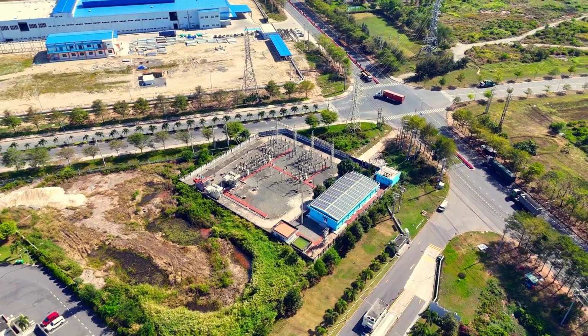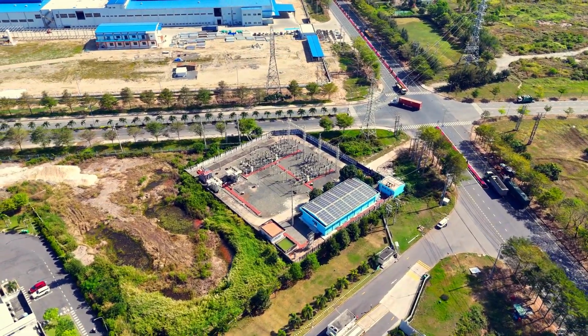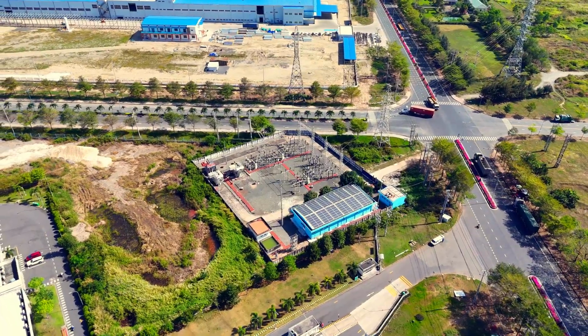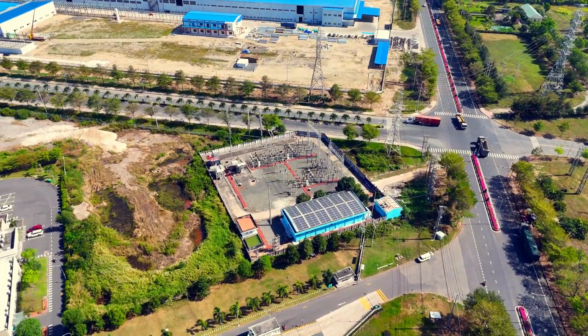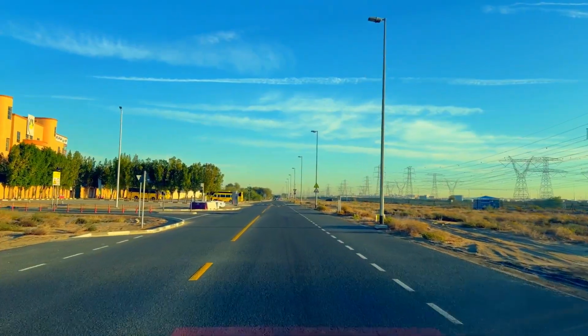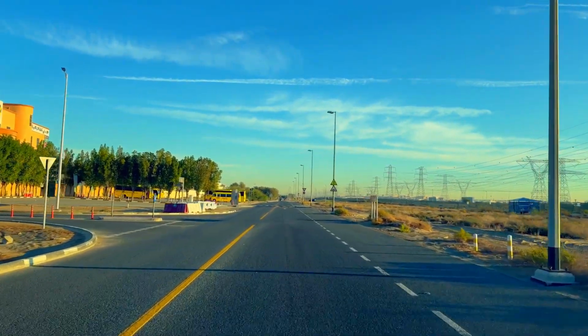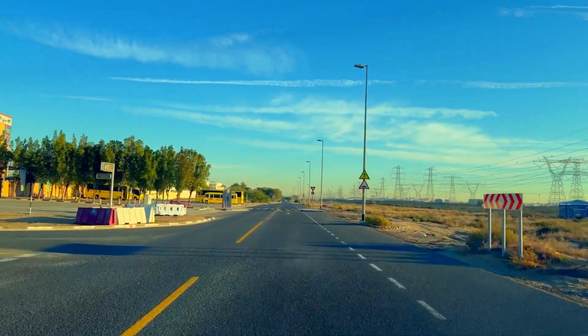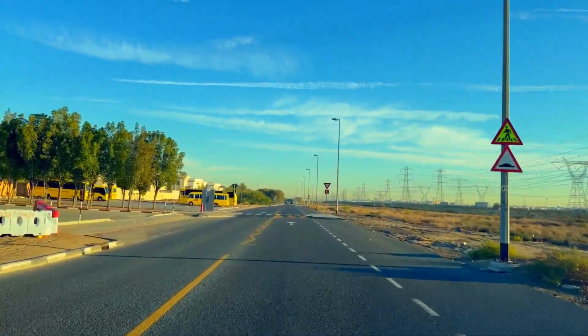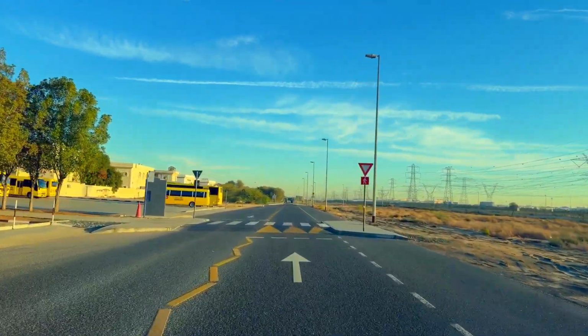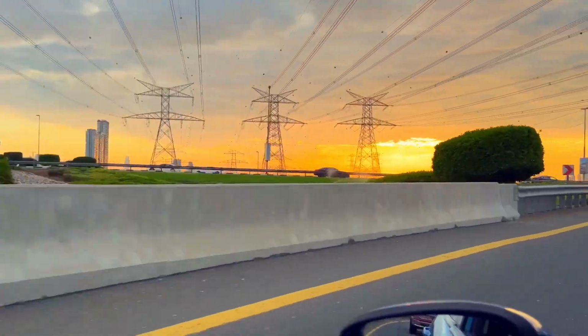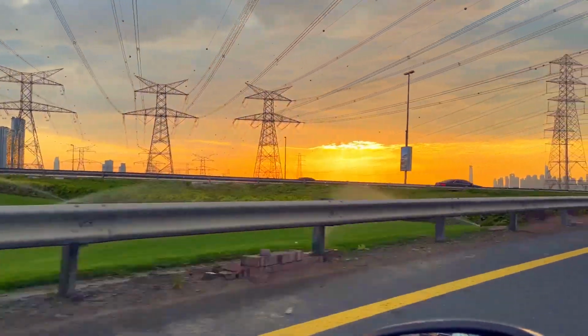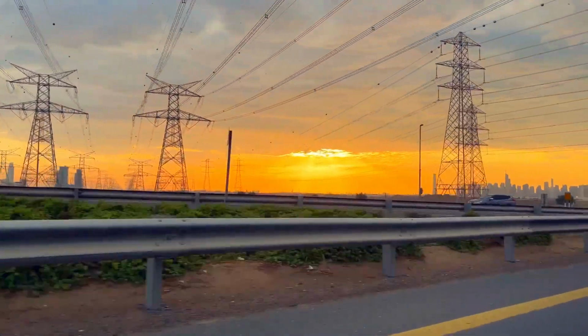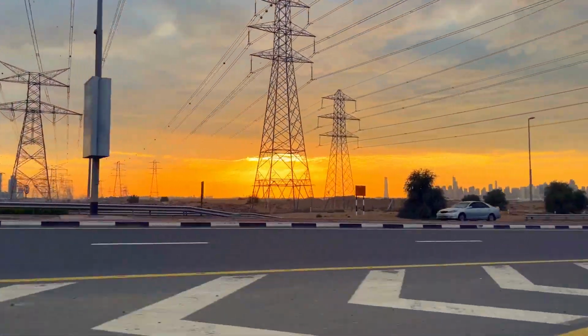But here's the tension the whole thing quietly rests on. Every bit of that protection depends on the relays being able to see a fault, and the way they see it is that sudden, violent spike in current when something goes wrong. That spike doesn't come from nowhere. It comes from the heavy spinning machines inside conventional power plants, which dump a huge surge of current into a fault the instant it appears. That surge is the signal.